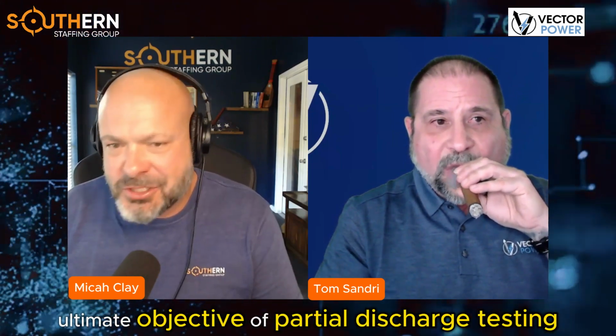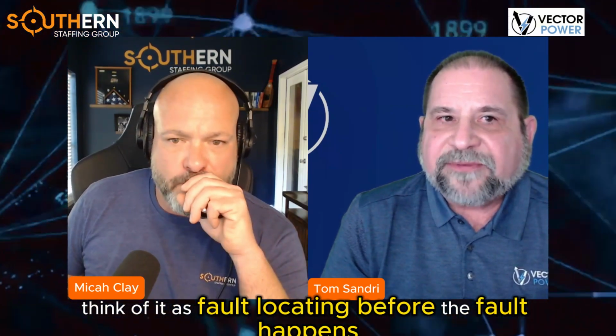Gotcha. I'm here to ask the stupid questions. So what is the ultimate objective of partial discharge testing? Why would a technician even need to do partial discharge testing? Think of it as fault locating before the fault happens. Gotcha. So prevent the unscheduled outage, detect that the problem is there so you can schedule a corrective action. You control when that circuit goes down rather than leaving it to fate.